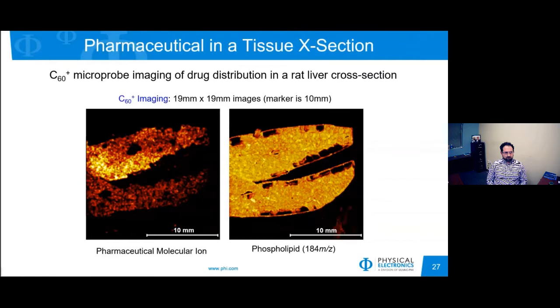How that's accomplished with TOF-SIMS is with mosaic mapping. The instrument collects a field of view roughly anywhere from a couple hundred microns to 600 microns, and then the sample moves underneath the ion beam to a new area and performs an analysis. It repeats this until it completes analysis of the defined area, and it stitches it all back together in post-processing. So as well as doing very small micron area sizes, you can do up to millimeter areas to really map out your sample and gain more information on a macro scale.